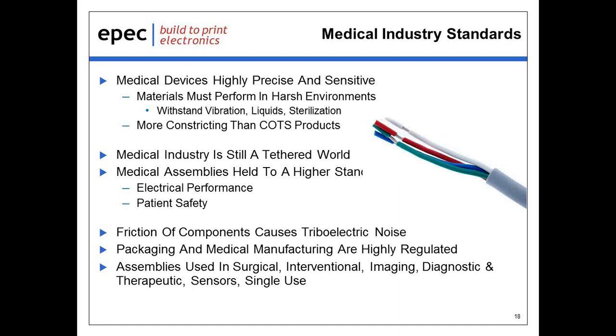From an electrical standpoint, performance is needed to ensure no false signals are transmitted over the assembly, or that the assembly transmits all information in a timely manner that's sent down there. One of the highest concerns when we're building a medical assembly is the issue of triboelectric noise. Triboelectric noise is the result of two components inside an assembly, be it conductors or a conductor and a shield, rubbing against each other and producing some type of noise or static that will cause false signals to be transmitted or cause a transmitted signal to be wiped out because of the noise. Medical assemblies need to be fully tested to make sure they're electrically sound.